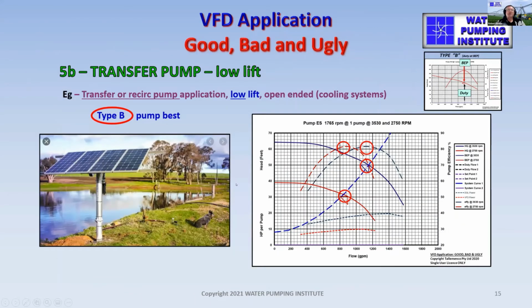And this might be a typical scenario where you have a solar powered system, and you can only pump as much as the available solar energy allows you to. So in this particular case, it is the perfect application where in the early morning and late afternoon, the pump output is only low, but it's operating at best efficiency point. So that's what I call a very good application for a VFD. And the VFD is an integral part of your solar system, where an inverter is required to convert the solar from DC to AC. So a solar system automatically includes a VFD.